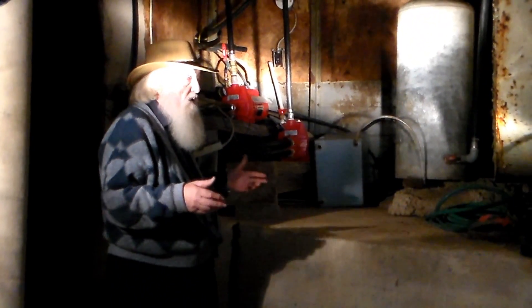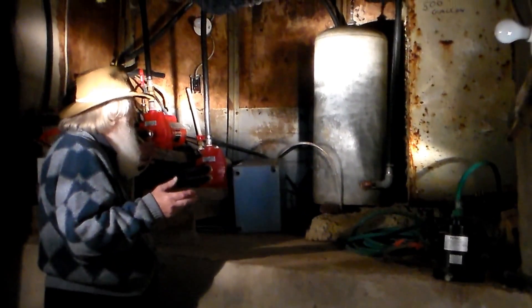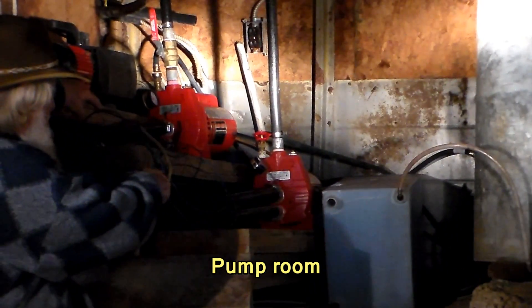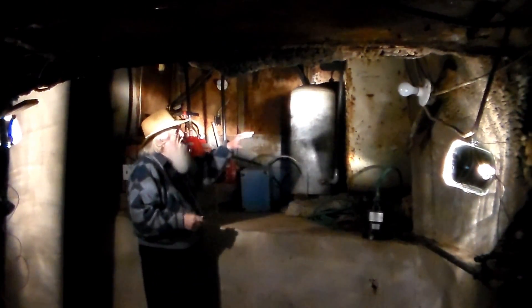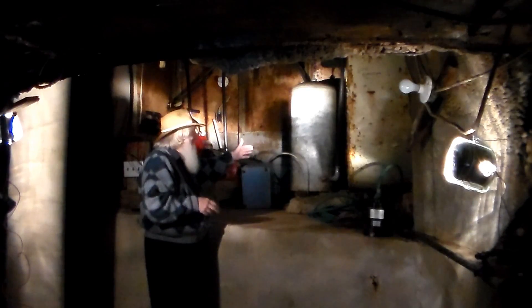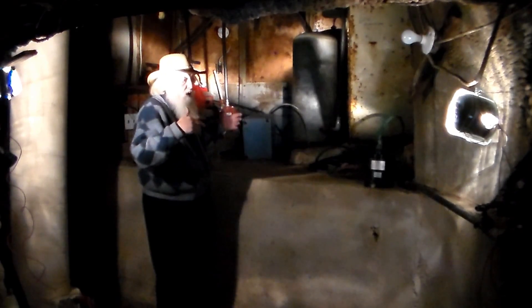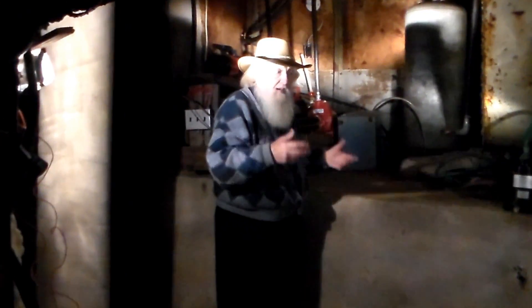This is the pump room, and this is the main supply of water to the shelter. The pump room gets the water out of the well. These are the two major pumps right here that we use for pumping water out of the well. They pump water out into this 500-gallon stainless steel settling tank where the water settles. From there we take the water through that pump and put it into the pressurized system, then move it up to the 5,000-gallon stainless steel holding tank.